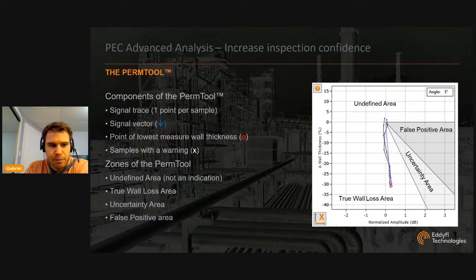There's different components to that PERM tool. So we've got a signal trace. We'll get a point for every single A-scan, as we mentioned. And then we're tracing a vector. So there's going to be a blue arrow that's pointing to the point of lowest wall thickness measurement within the cursor. So typically, you're looking at an indication, so you're interested in where there is the most wall loss. And you want that signal curve and the vector to have similar shapes to match, basically, for the tool to be used accurately. We'll put a dot around the point where the cursor is centered and an X if there's a warning present within the signal trace.